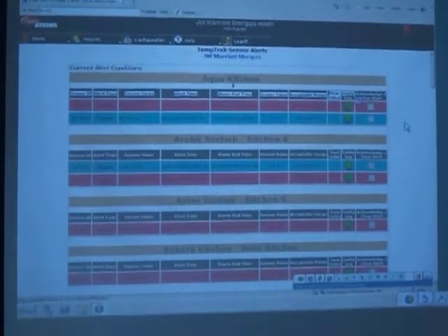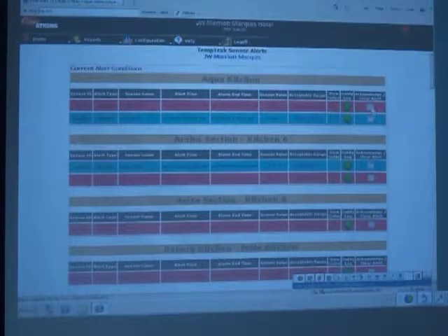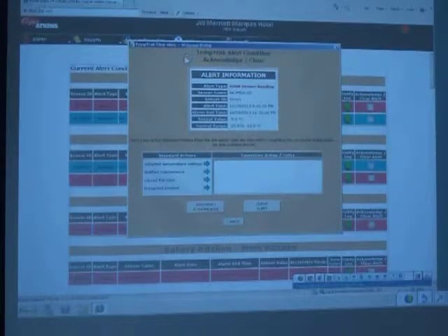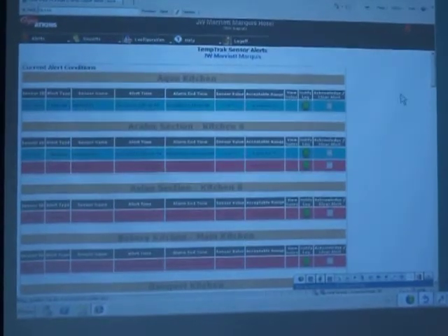and of the alert. In order to clear an alert, we will check this box and acknowledge the alert, which will open a window which will give you again specific information about the alert, starting from high sensor reading, name, fridge, number, temperature, critical limit. We can now enter standard corrective actions: close the door, notify maintenance, discard products, whatever. You can also enter corrective actions manually and clear alarms manually by clicking the clear alert box. So now the alarm has been cleared.